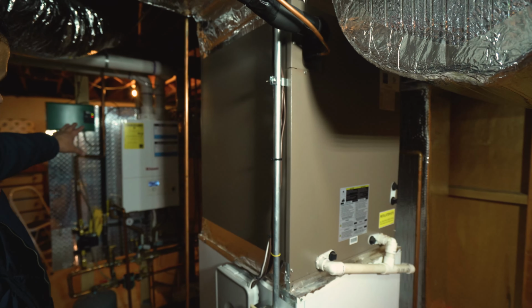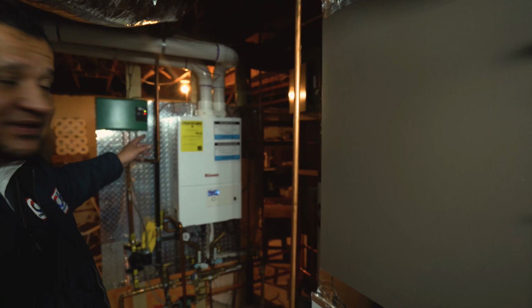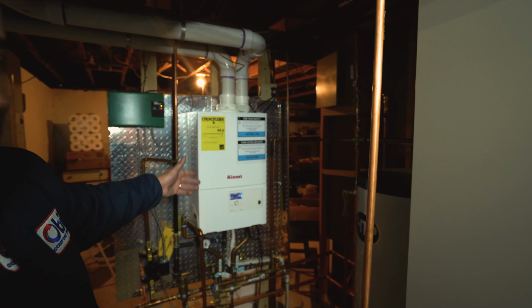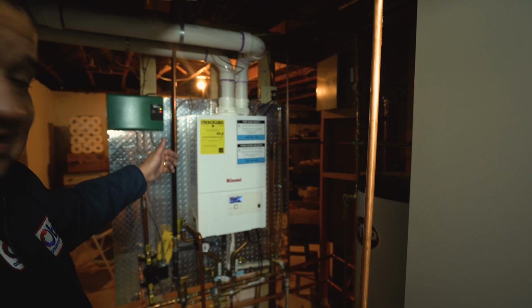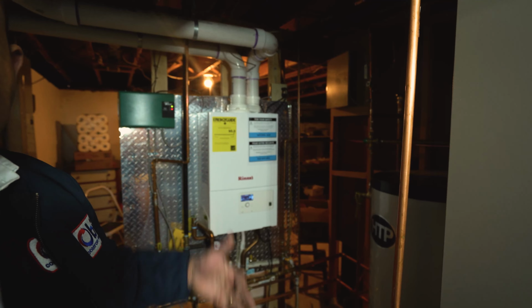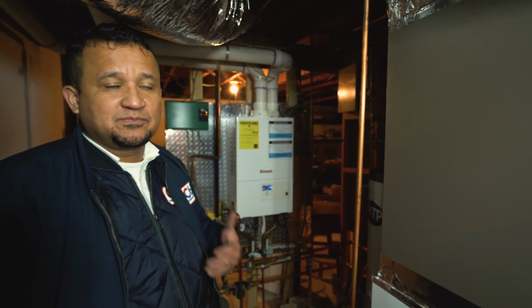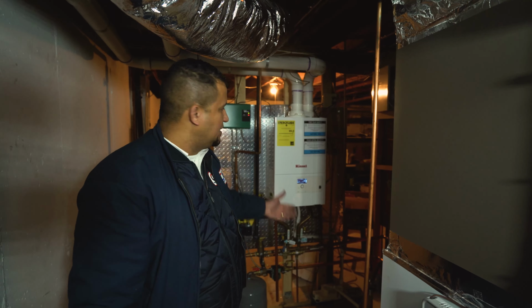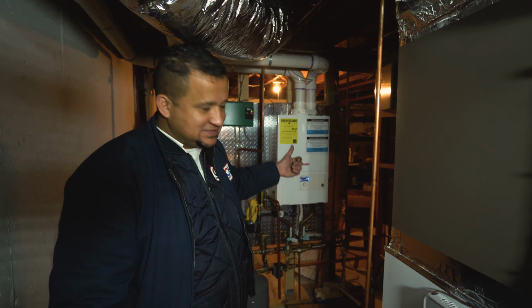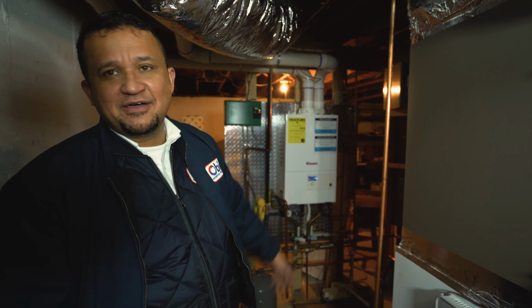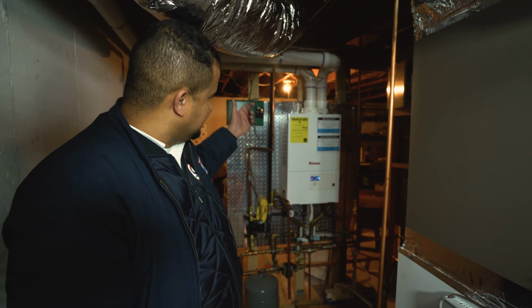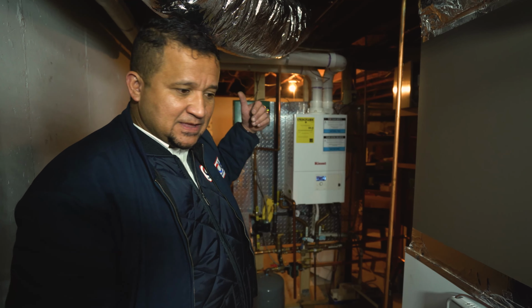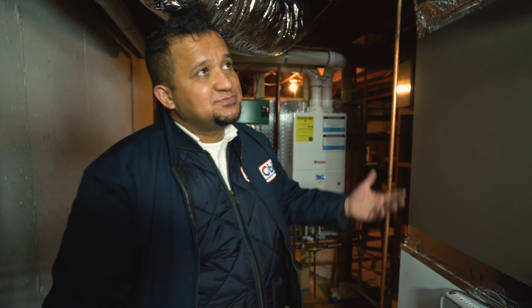We also changed the parameters in here on the boiler. This was not done properly. They use an outdoor sensor for this unit, but on days like this, when the temperature is not so cold outside, the boiler was heating up only to 120 degrees, so she never had enough hot water. So we changed that too. Basically, that's pretty much it.